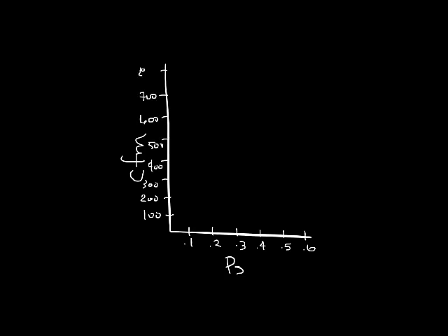So now let's draw a fan curve. For fan boxes, the horizontal axis of the fan curve shows pressure, and the vertical axis is CFM. Other products you may see the axis switched. Let me add some pressures and airflows. The fan curve will show a maximum and minimum airflow range for that size unit. It'll look something like this. The top line is the maximum line, the bottom line is the minimum line.